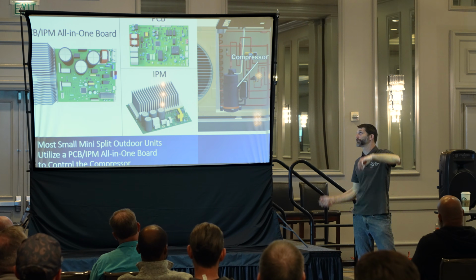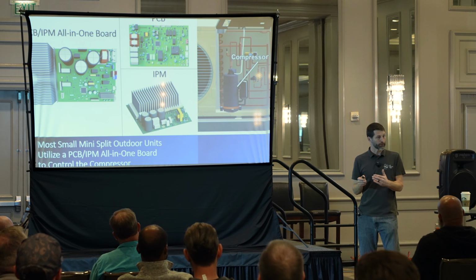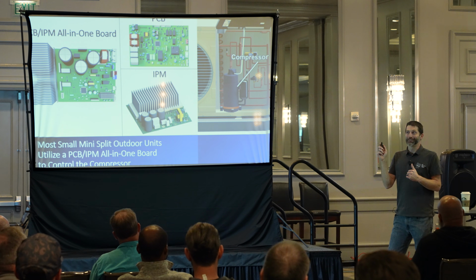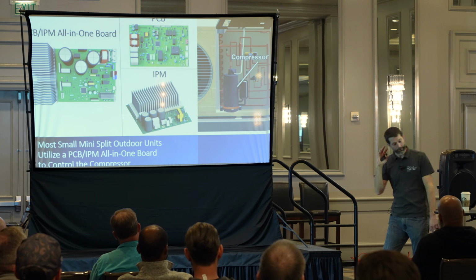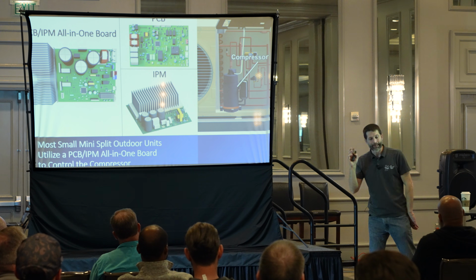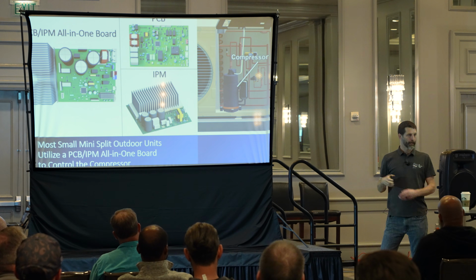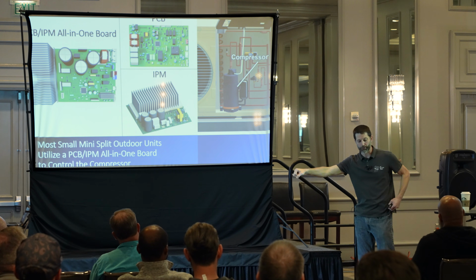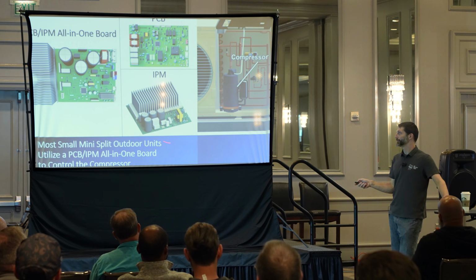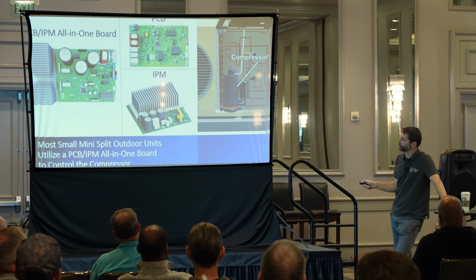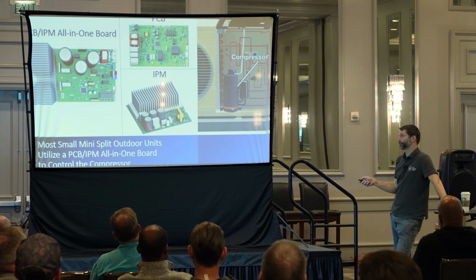If you're going to service a mini split, what I'm going to tell you you should do is put it into standby mode, say at the remote or whatever, and listen and wait for the compressor to stop. That's when you pull the electrical disconnect. If you're pulling the electrical disconnect while the compressor is running, the shock is happening in here in the IPM. You could literally be causing damage to the system at the IPM module by pulling the disconnect while the thing is running. And I know that sounds funny, but that actually is happening.